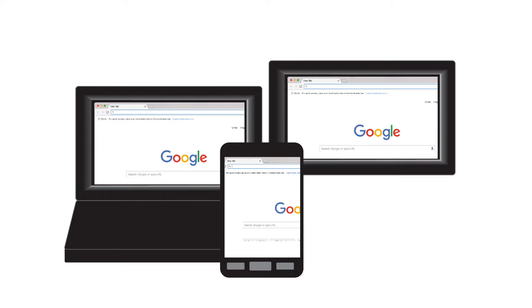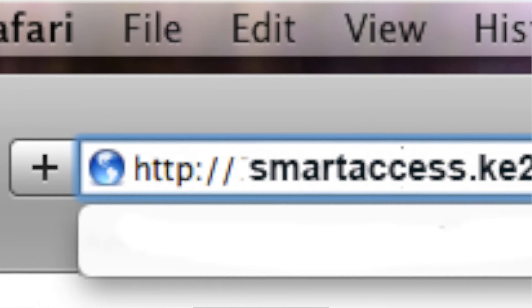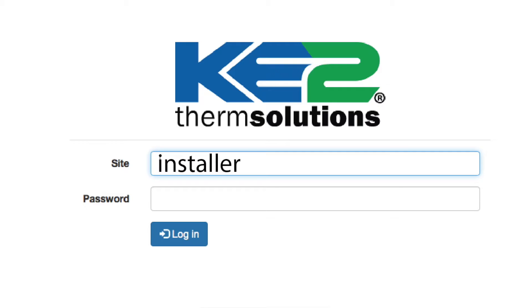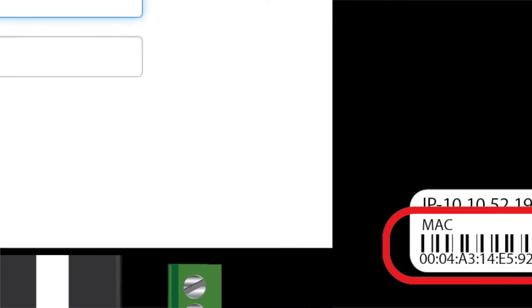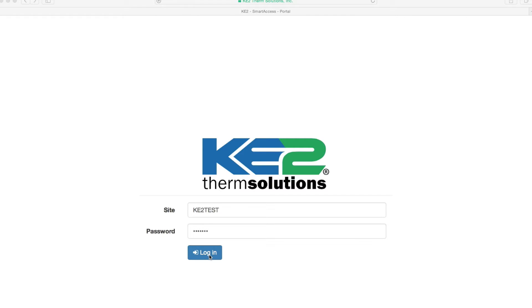On your PC, phone, or tablet, enter smartaccess.ke2therm.net in your web browser's address bar. If you haven't designated a site for the controller, like I described in the other videos, once you reach the login page you will enter the default information. The default site information is Installer and the password is the controller's MAC address found on the back of the controller. Enter the information and click login.